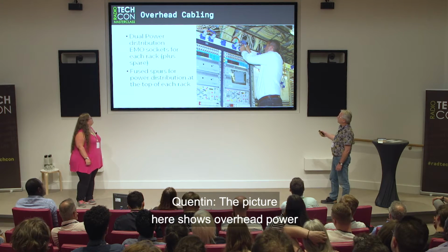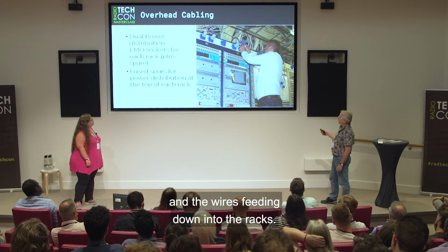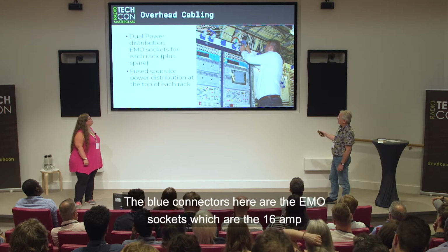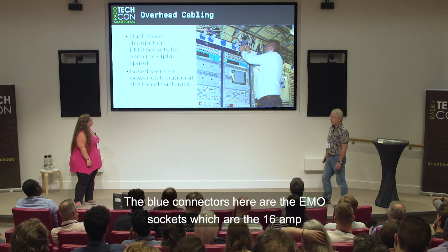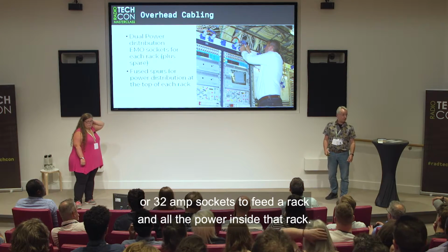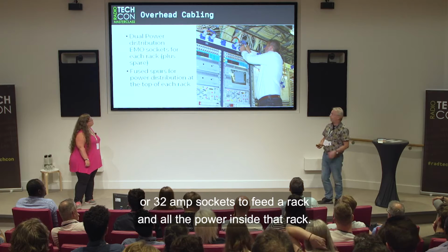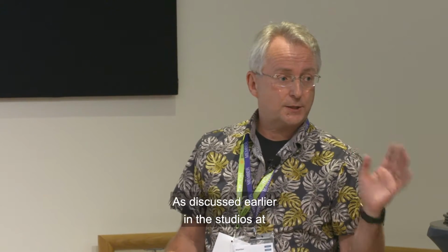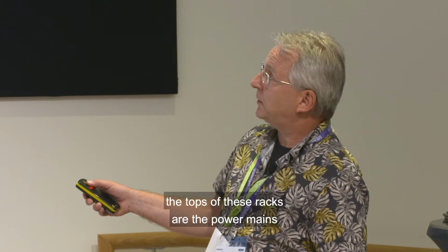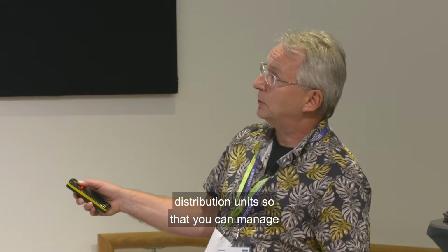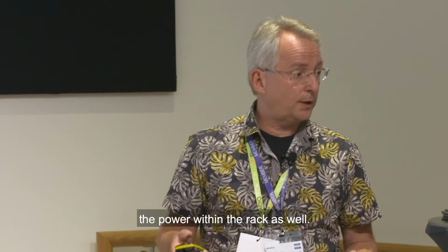This picture shows overhead power and the wires feeding down into the racks. The blue connectors are the EMO sockets, which are 16 amp or 32 amp sockets to feed a rack and all the power inside it. As discussed earlier, at the tops of these racks are the power mains distribution units, so you can manage the power within the rack as well.